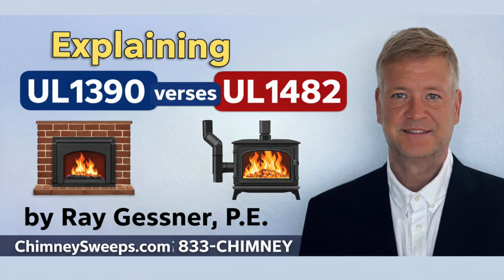And that realization points us directly to the biggest exclusion listed in UL 1390. Section 1.7 explicitly states, this standard does not cover freestanding solid fuel space heaters. It literally abandons you if you want a classic stove on legs. Yeah, it gives you the exact standard to look for instead, which is UL 1482. And that perfectly establishes the other half of our regulatory ecosystem. If 1390 is the strict standard for shoving a fire into a brick hole in the wall, UL 1482 is the veteran standard that governs the freestanding units standing out in the open room.